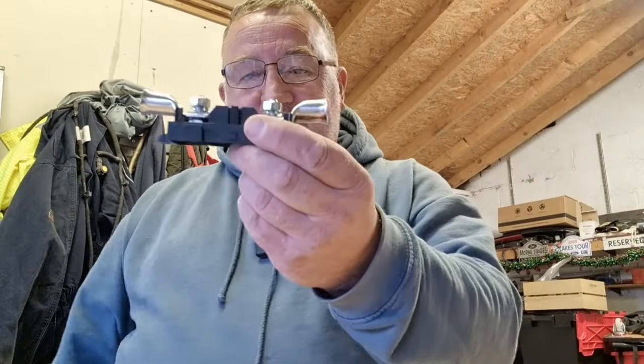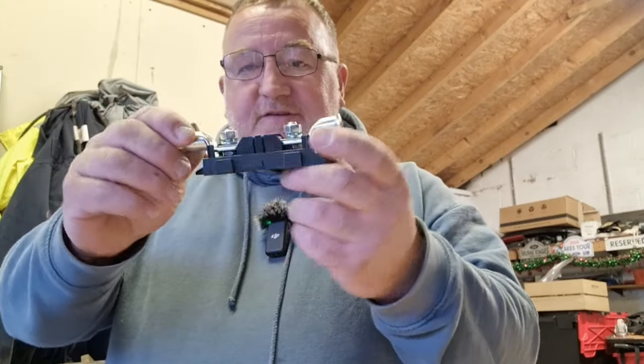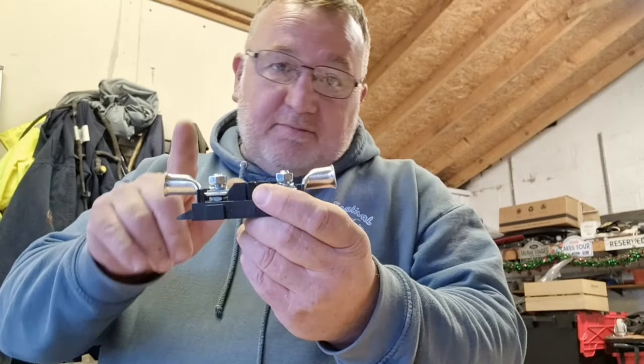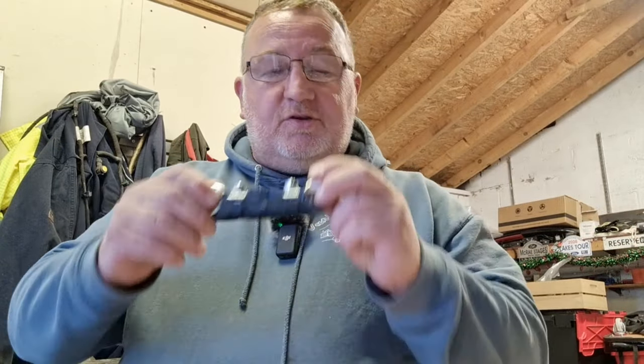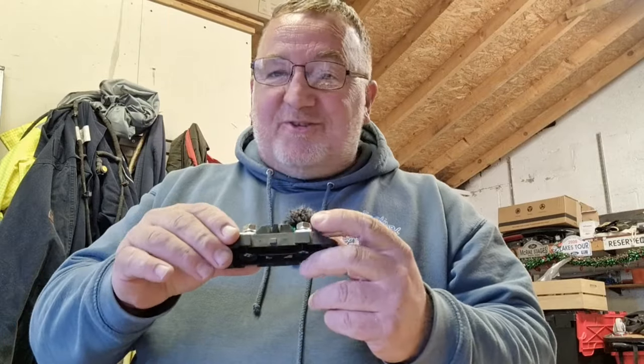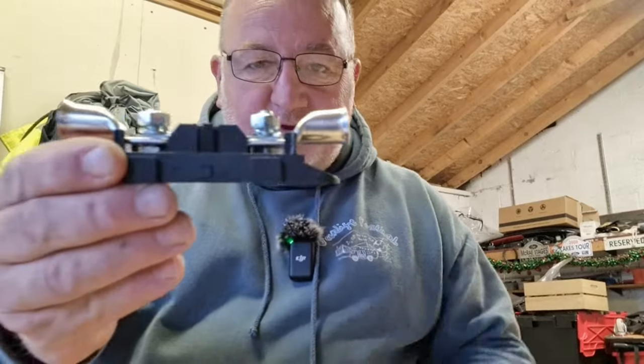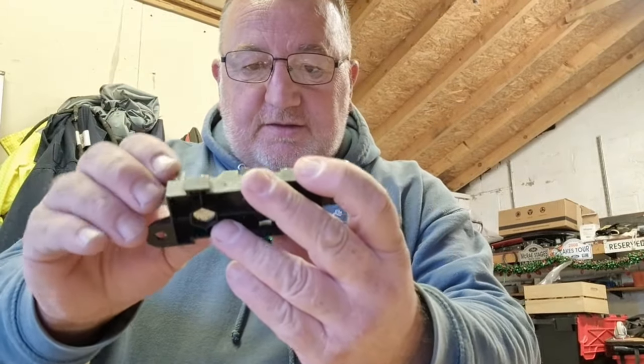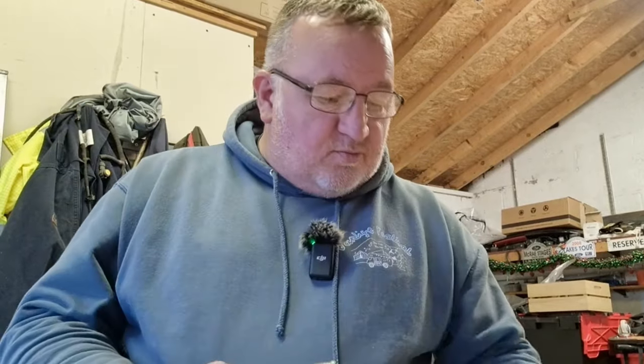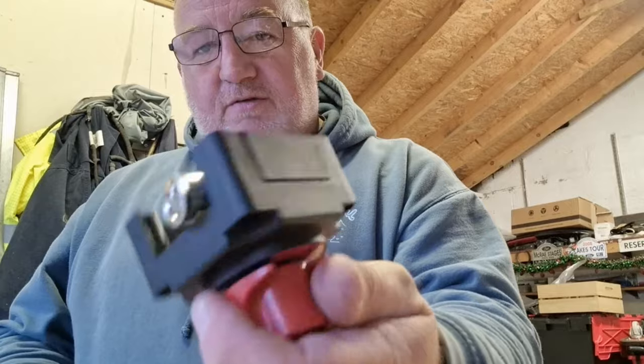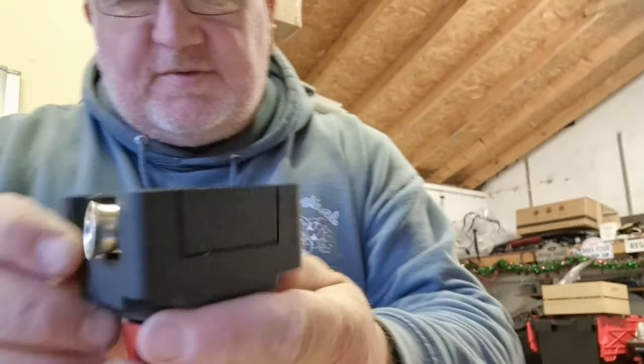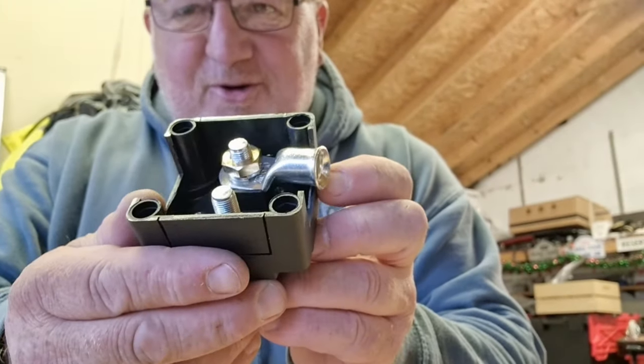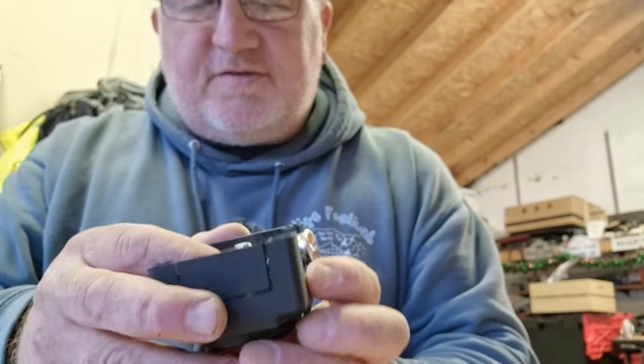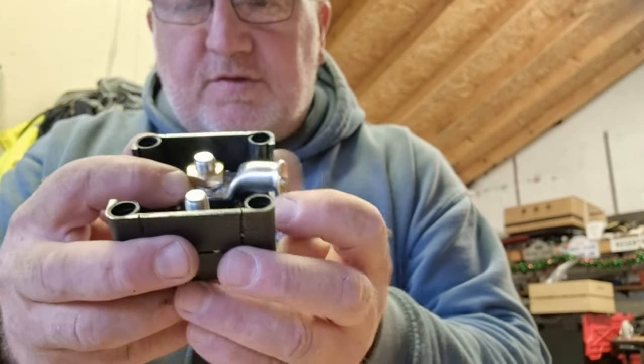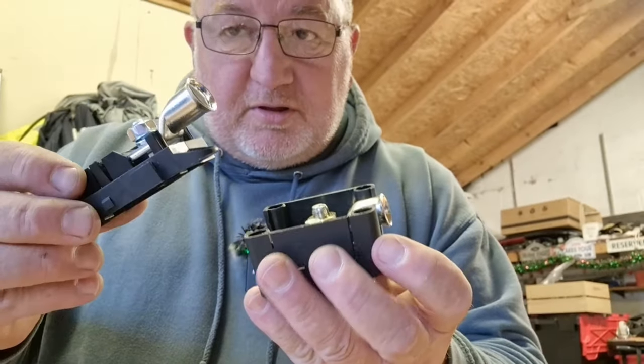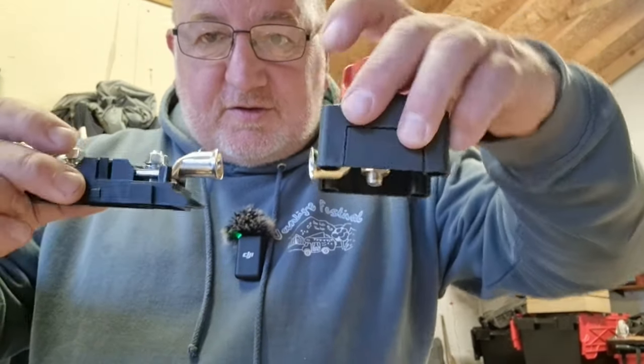Something else to consider is the orientation of your lugs. I've seen people make cables and then make them fit the installation, and that's not how it works. You make your cables to fit your installation, not the other way around. Look at that, that shows you how that is meant to sit. Basically, they will go that way. Now, when you come to use an isolator, they're the opposite way around, so it's hard to show you that. There you go, so that sits on the bottom again. If you tried to put it on the top, it wouldn't sit right. So we need to make sure that, when we build our cables, both ends up in the correct orientation. That's the way they would sit.